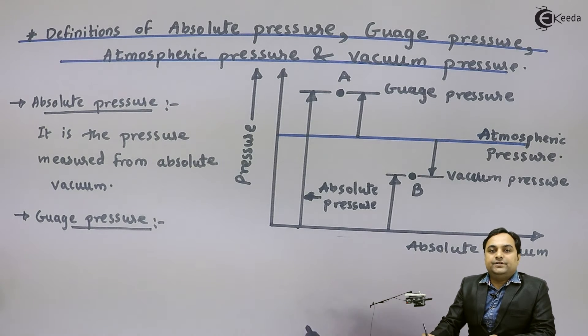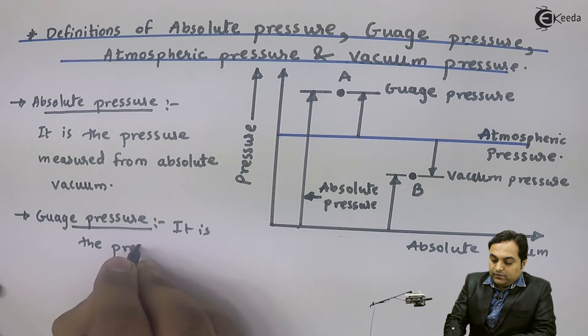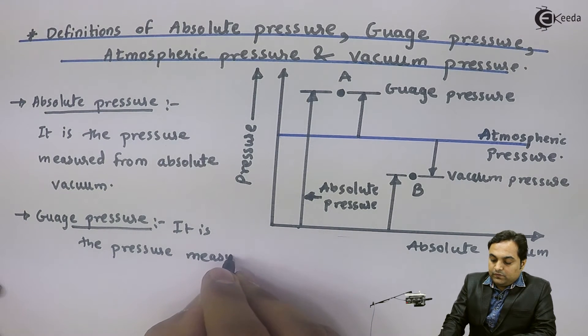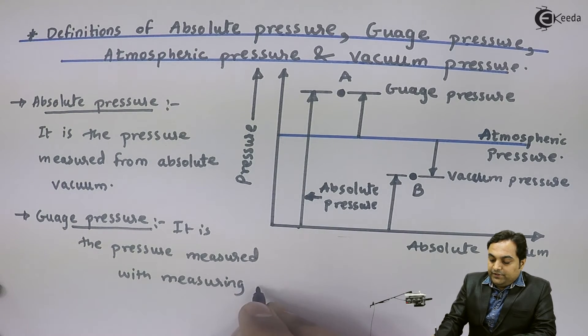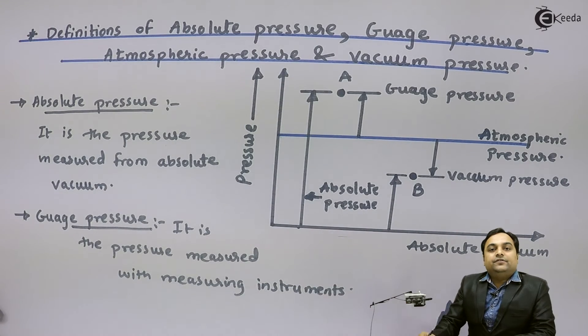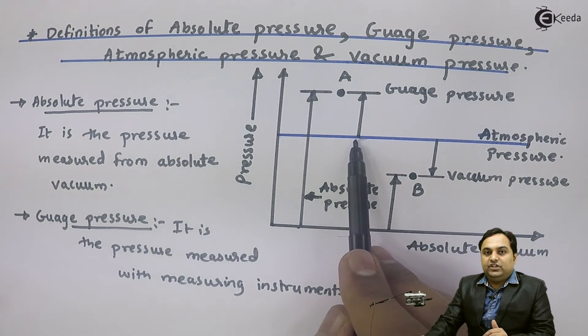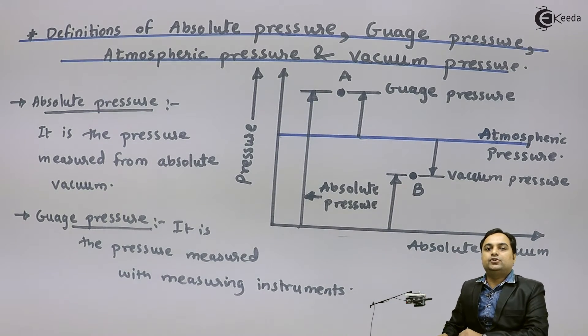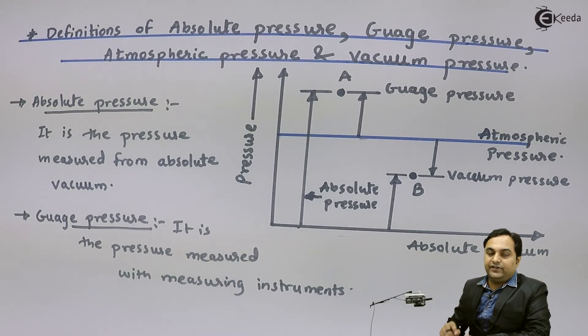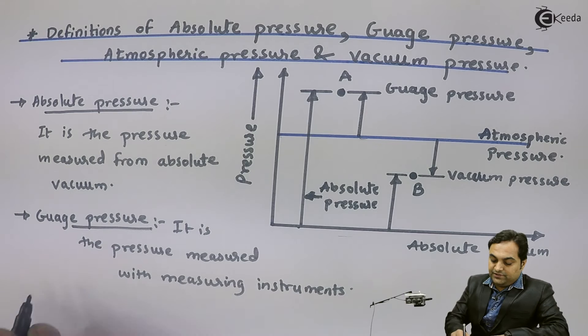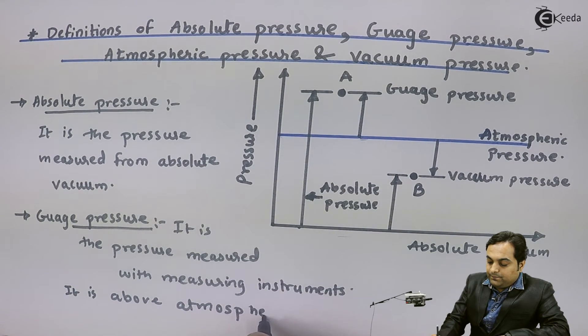Next is gauge pressure. Gauge pressure is the pressure which we measure with the help of measuring instruments. When we are measuring gauge pressure, our reference is atmospheric pressure — it means we take atmospheric pressure as zero and then start measuring. The measuring instruments used to measure gauge pressure start from a zero reading, and that zero reading indicates atmospheric pressure. So gauge pressure is the pressure measured with measuring instruments and it is above atmospheric pressure.